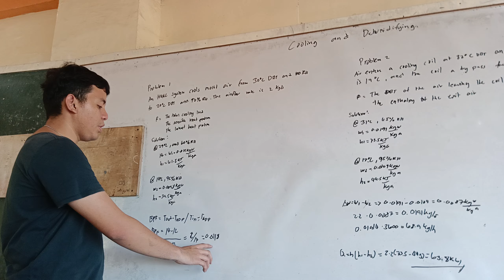Problem 2: air enters a cooling coil at 32 degrees dBT and 65% RH. The coil surface temperature is 14 Celsius, and the coil has a bypass factor of 0.2. Required: the dBT of the air leaving the coil and the enthalpy of the exit air.